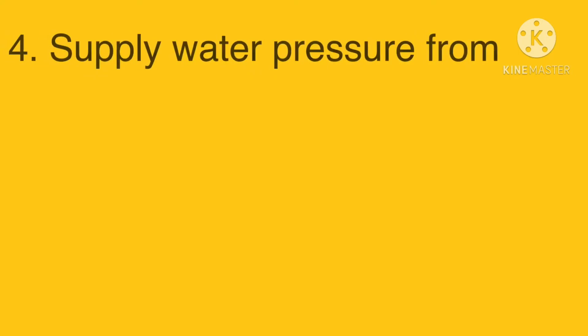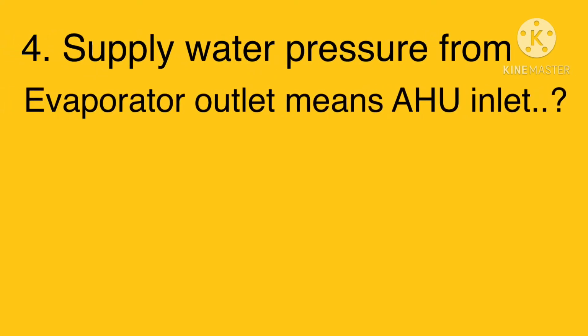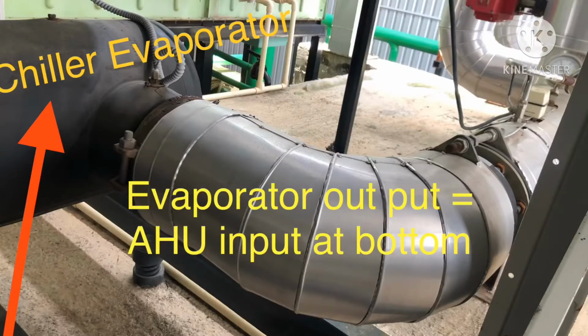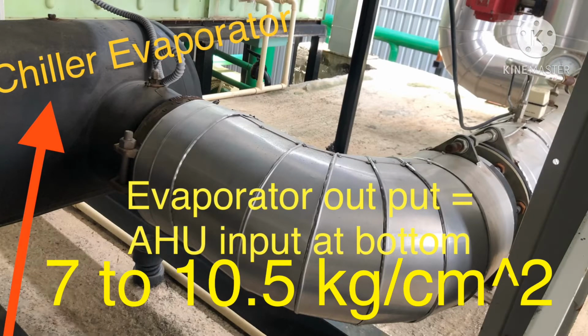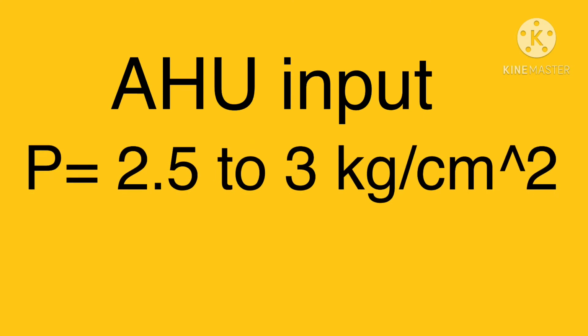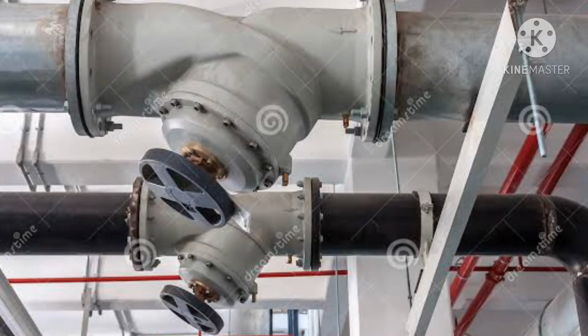What is the pressure from the evaporator outlet towards the AHU inlet supply water? Here the pressure is around 7 to 10.5 kg per centimeter square. This supply water pressure depends on the height of the building, the number of AHUs and the vertical length of the pipeline. But the requirement is that 2.5 to 3 kg per centimeter square pressure is enough to get sufficient cooling efficiency. This required pressure of 2.5 to 3 kg per centimeter square can be achieved by using balancing valves at the supply water lines towards the AHU or CSU units.